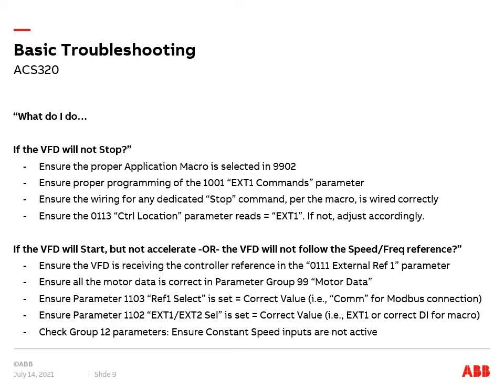What if the VFD will start but not accelerate, or the VFD will not follow the speed or frequency reference? Ensure the VFD is receiving the controller reference in the 0111 external ref1 parameter. Ensure all the motor data is correct in parameter group 99 motor data. Check parameter 1103 ref1 select and ensure it is set equal to the correct value — for example, com if you are using a Modbus connection.